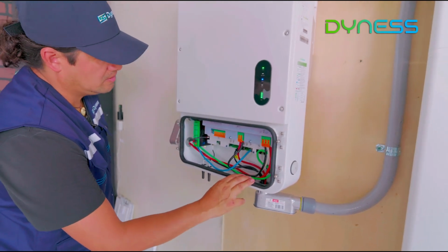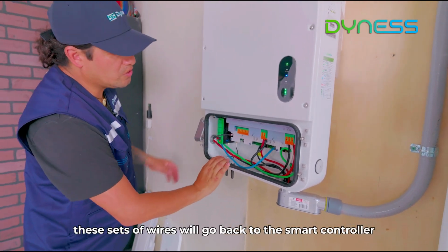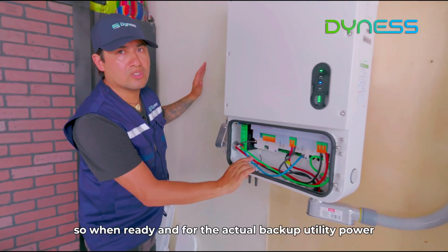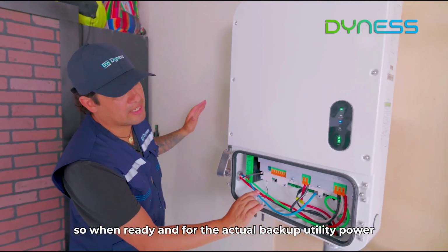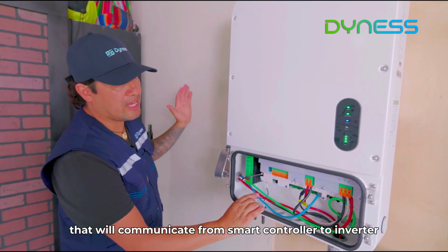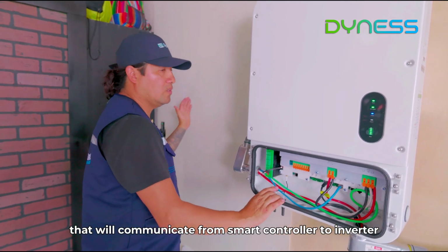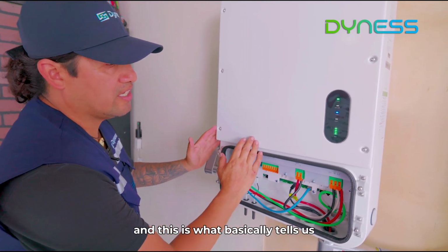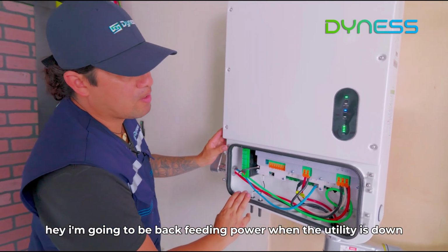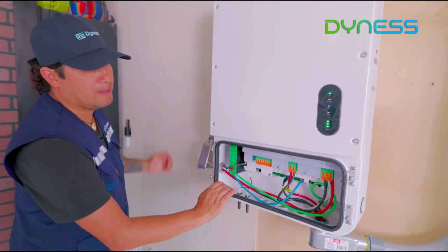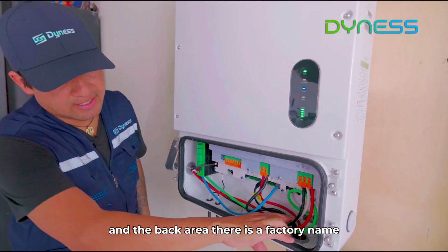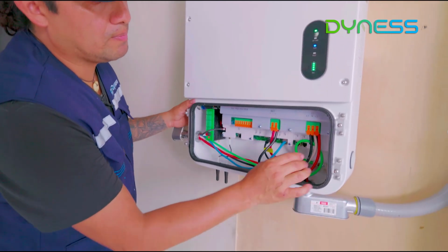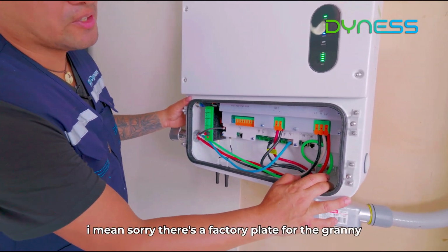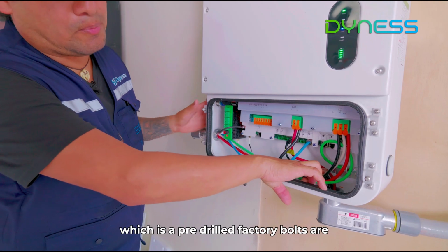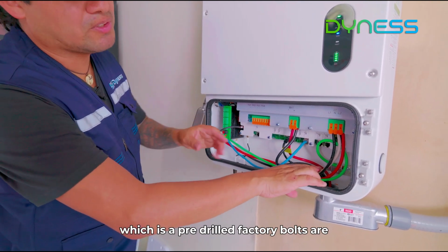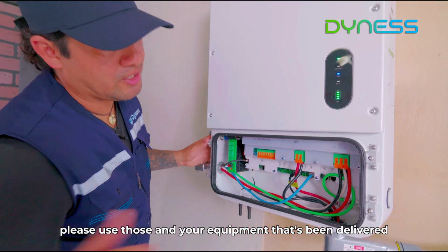These sets of wires will go back to the smart controller. So when ready, and for the actual backup utility power, that'll communicate from smart controller to inverter, and this is what basically tells us, hey, I'm going to be back feeding power when the utility is down. In the back area, there is a factory plate for the grounding, and the pre-drilled factory bolts are in the back. Please use those and your equipment that's been delivered.